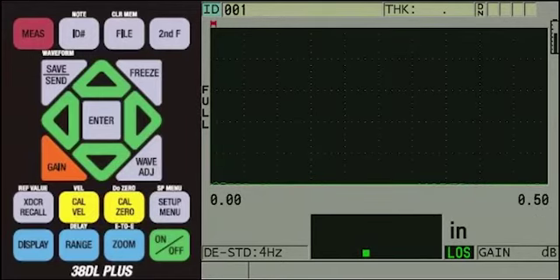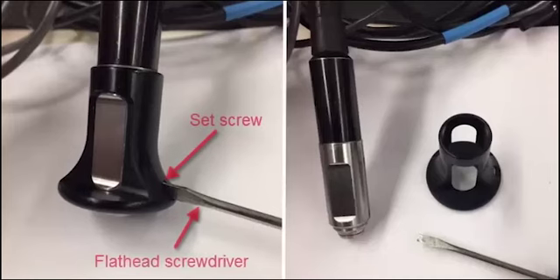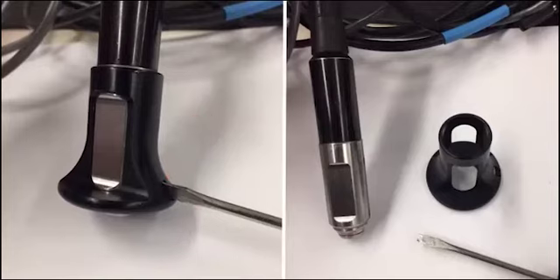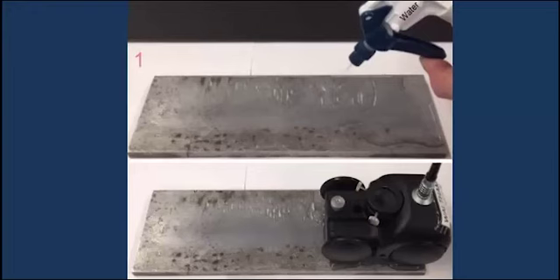We will use the waveform display to ensure that the D790-SM is inserted into the B-scan Buggy in a way that provides good signals on screen. Next, we will need to use a flathead screwdriver to remove the bell housing from the D790-SM transducer so it can fit in the probe holder of the B-scan Buggy. Once the bell housing is removed, you can apply water to the surface of the aluminum sample and then place the Buggy onto the aluminum plate.